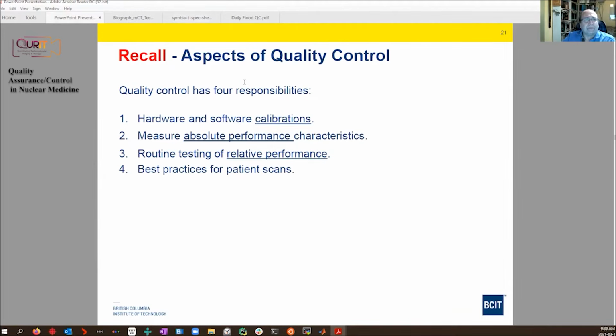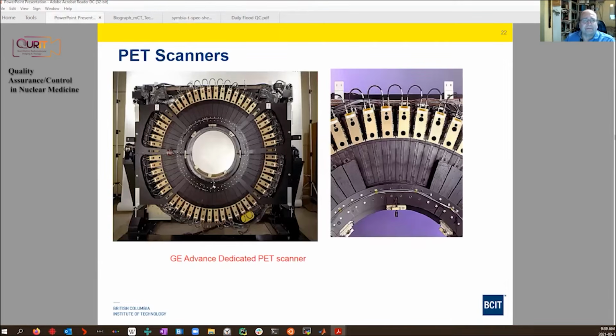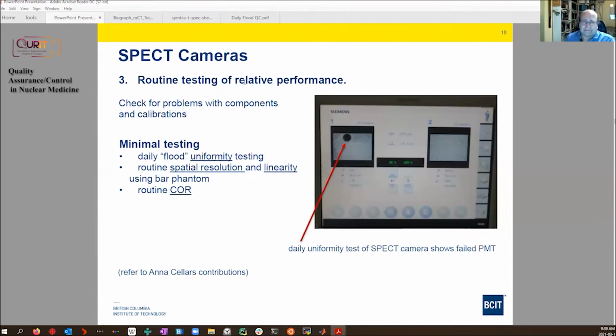So that was absolute measurements for acceptance testing. Again, routine testing, I was toying with the idea of going through this in detail, but covering this wide swath of QC, we can't go through them. The minimal testing that's done is that SPECT cameras usually have a daily uniformity flood, which is just setting up a flood field and measuring the uniformity, visually inspecting it, and also recording the specific quantitative values that are extracted from it. And let me just pull up one more thing for us.